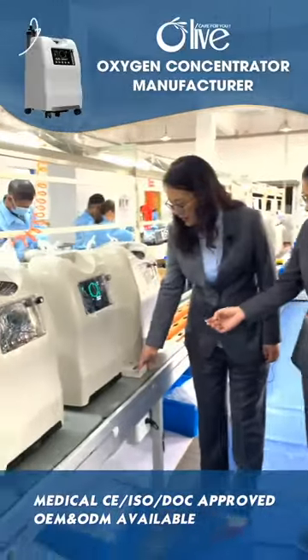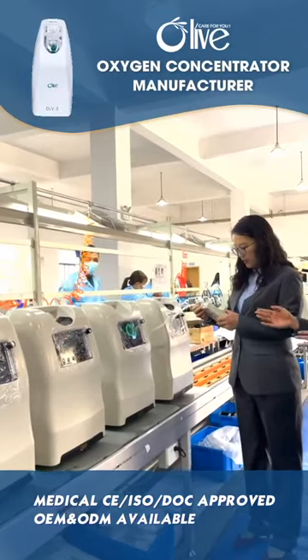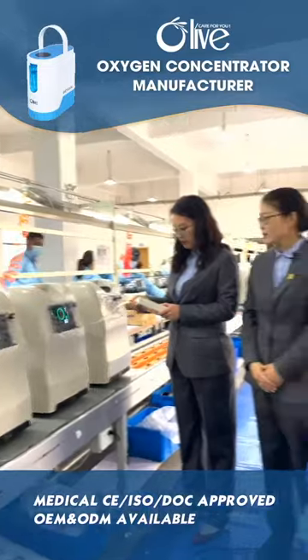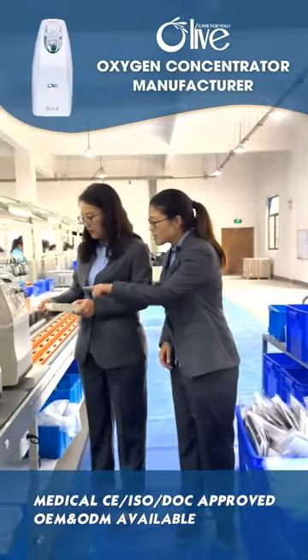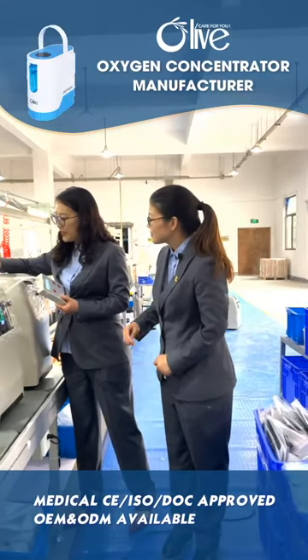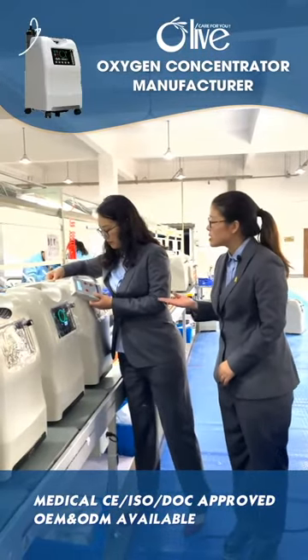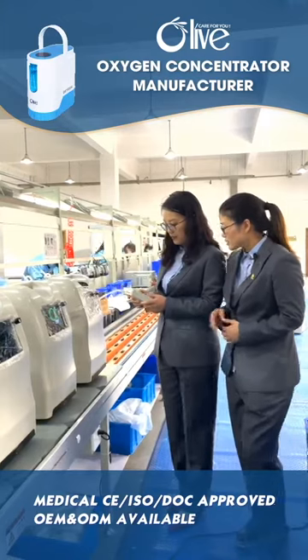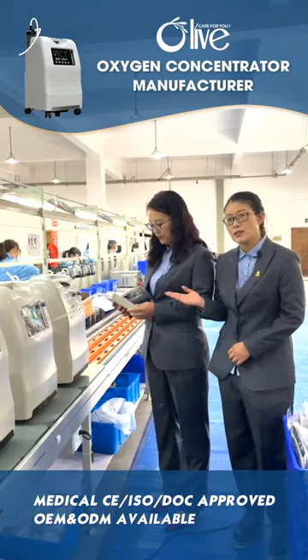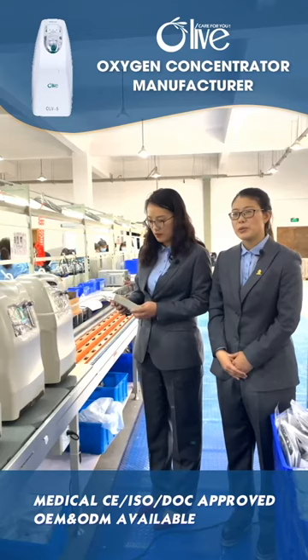I told you, this is the oxygen analyzer. You will use this device to check the purity of the oxygen concentrator. This is the on-off button. So we connect this tube to the device, connecting it with the oxygen outlet. Press this button, then check the numbers on this device, whether it can reach 93%.